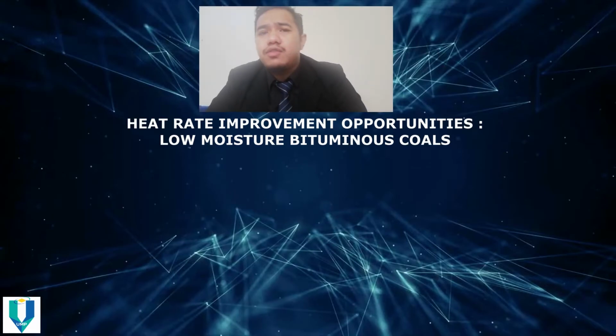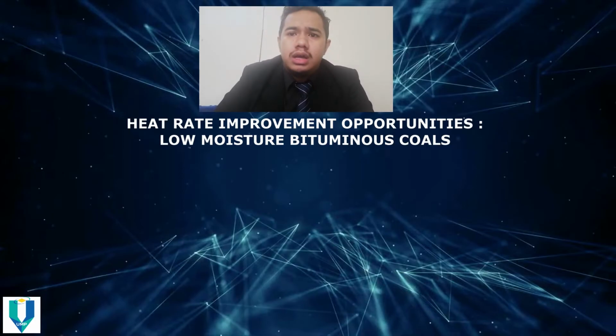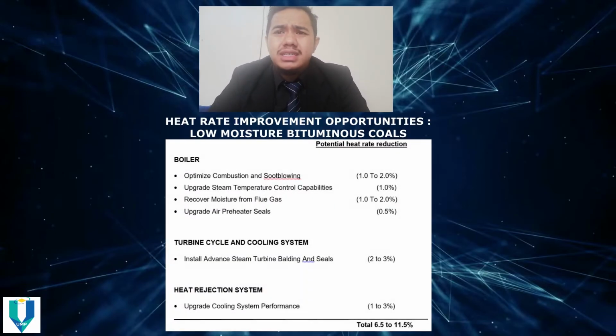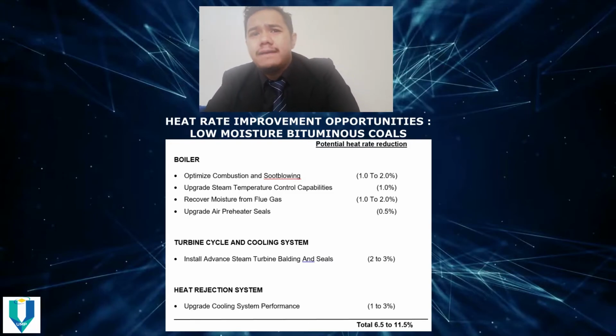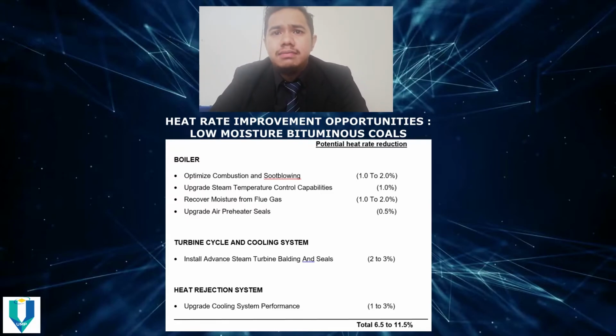The heat rate improvement opportunities for low moisture bituminous coals. For the boiler, the potential heat rate reduction for optimized combustion and soot blowing is from 1 to 2%. For upgrading steam temperature and control capabilities, it is 1% only. The potential heat rate reduction for recovering moisture from flue gas is from 1 to 2%. And for upgrading the air preheater, it is 0.5%.